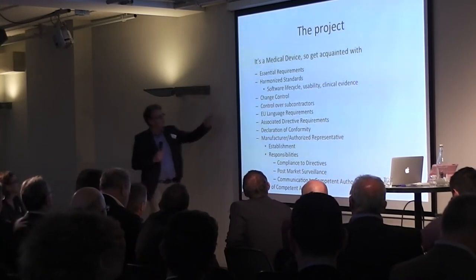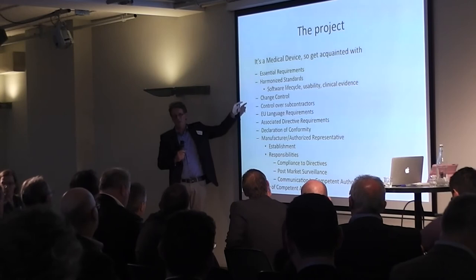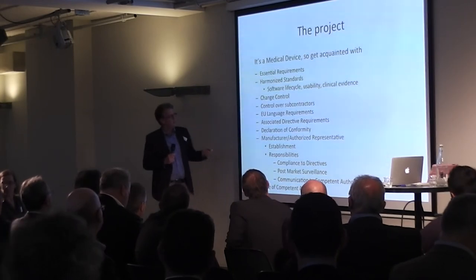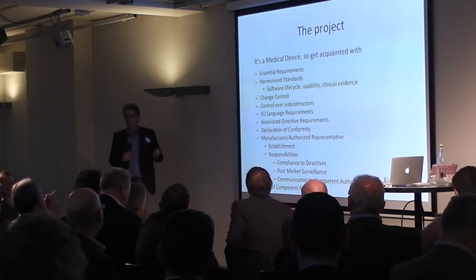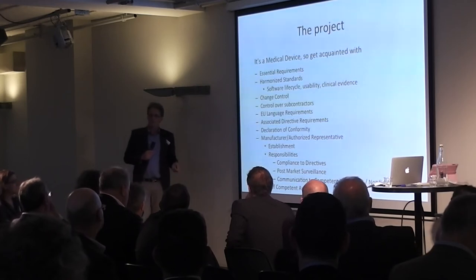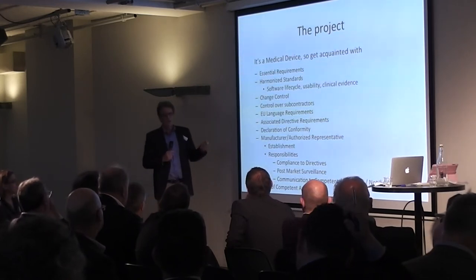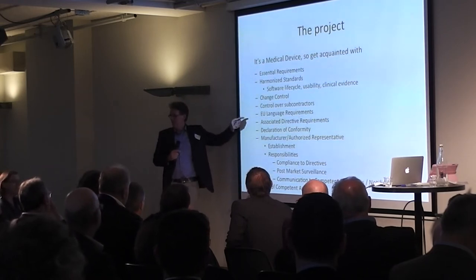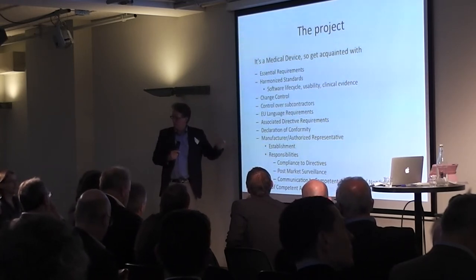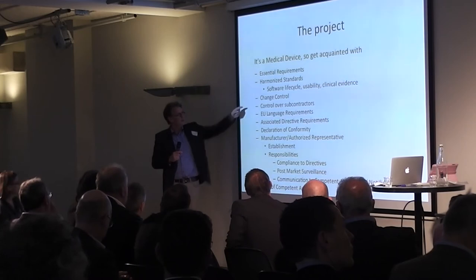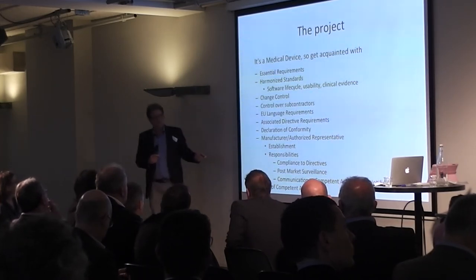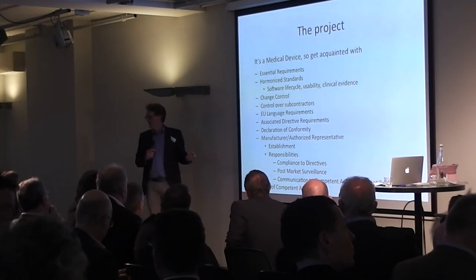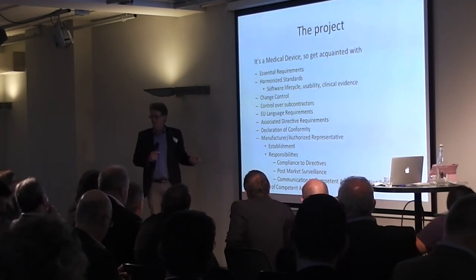The directive and subsequent status — that's important. And then, working in your project: change control. So if the product is on the market, any change to the product — does it have an effect on the performance? If you change something, it probably has a clinical impact, so all these processes are part of your quality system. If you outsource software or verification activities to an external test house, you need to have control — do they do what they should? Do they have a system that matches yours?